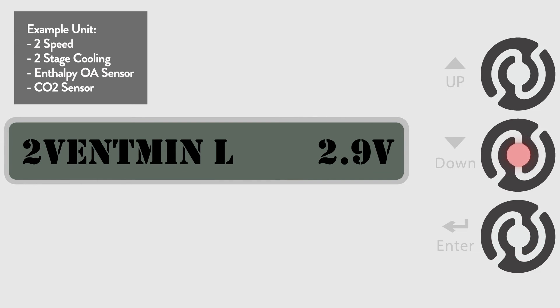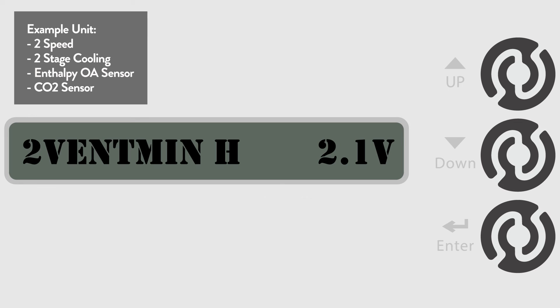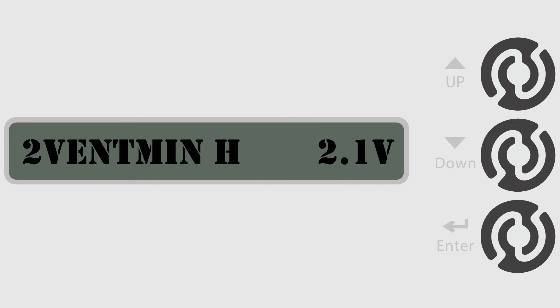Our objective is setting up a 2-speed unit with 2-stage cooling using an enthalpy outside air sensor and a CO2 sensor. Lastly, go to the 2 Vent Min H menu to set the CO2 sensor's minimum non-free cooling position when the fan is in high speed. The default is 2.3 volts, but we are going to change that to 2.1 volts. Our objective of setting up a 2-speed unit with 2-stage cooling using an enthalpy outside air sensor and a CO2 sensor is now complete.